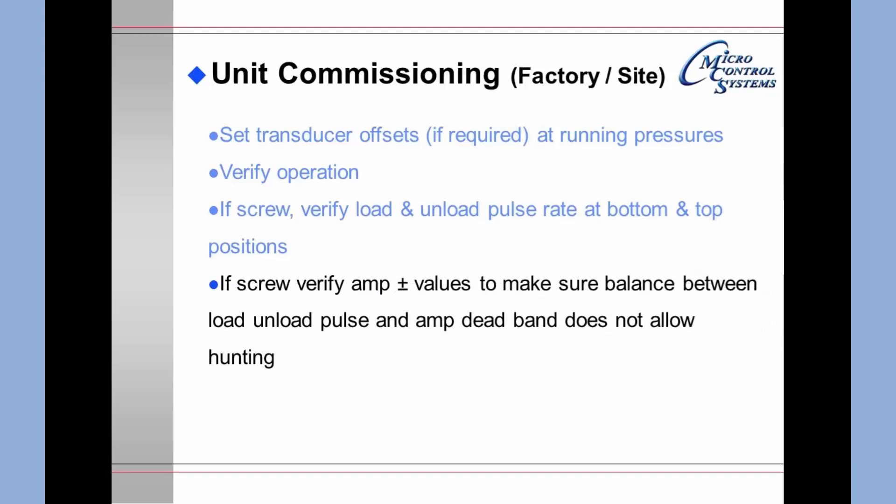If it's a screw, verify the amps plus or minus values to make sure that they balance between the load and the unload pulse and that the amp dead band does not allow hunting. What you are looking for here is that if a load pulse is made and the unit drifts too far, then the amp dead band is not large enough and the machine will hunt.